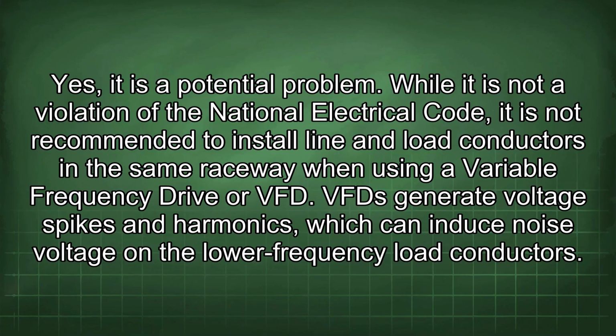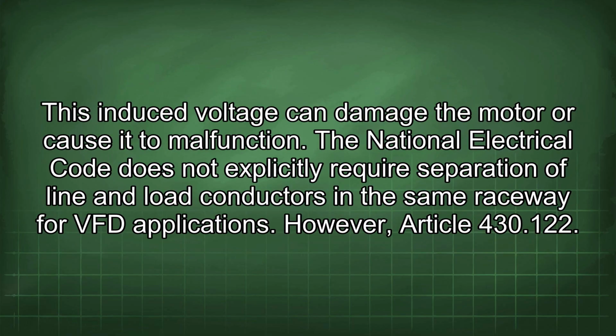Yes, it is a potential problem. While it is not a violation of the National Electrical Code, it is not recommended to install line and load conductors in the same raceway when using a variable frequency drive, or VFD. VFDs generate voltage spikes and harmonics, which can induce noise voltage in the lower frequency load conductors. This induced voltage can damage the motor or cause it to malfunction.